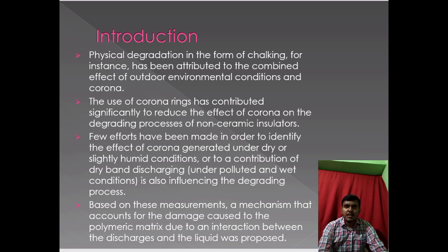On polymers having intrinsic highly hydrophobic properties such as EPDM and silicone rubber, deposition of surface charge has been identified as a factor leading to the temporary loss of hydrophobicity. It is also a well known fact that exposure of a dielectric surface to corona gives rise to space charge, and the rate at which the space charge accumulates within the polymer depends on the type and magnitude of the applied electrical supply. This defines the extent to which corona discharges may provoke the degradation of polymer physical and electrochemical properties. According to the reports, the average lifetime of a polymer insulator used in a DC system is expected to be shorter in comparison to that of an AC insulator, and that will be explained in the upcoming slide.